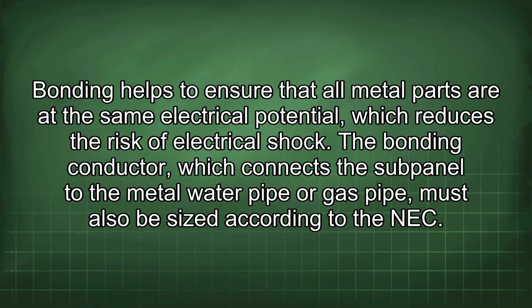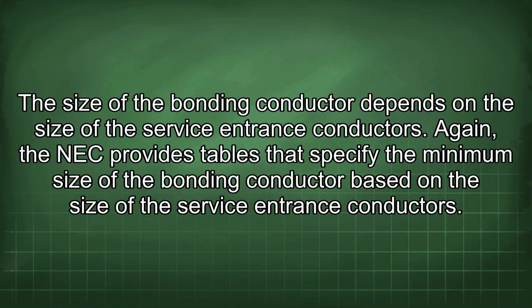The bonding conductor, which connects the subpanel to the metal water pipe or gas pipe, must also be sized according to the NEC. The size of the bonding conductor depends on the size of the service entrance conductors. Again, the NEC provides tables that specify the minimum size of the bonding conductor based on the size of the service entrance conductors.